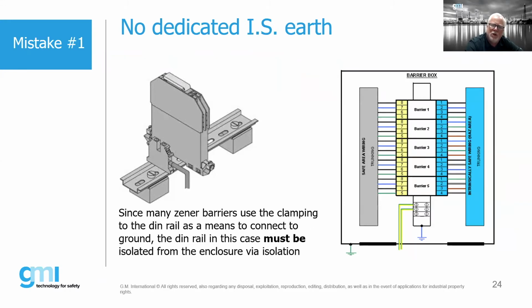So we want to make sure that when we are utilizing Zener diode type barriers, and we're mounting them to a DIN rail of some sort, that DIN rail is isolated from the enclosure. Assuming we're using a metallic enclosure, we have to have proper insulation. This is one of the biggest issues that I see when I go out and do inspections on intrinsic safety with regards to Zener barriers: not having a dedicated IS earth.